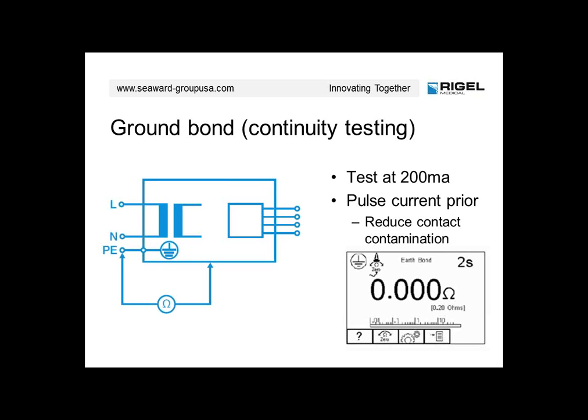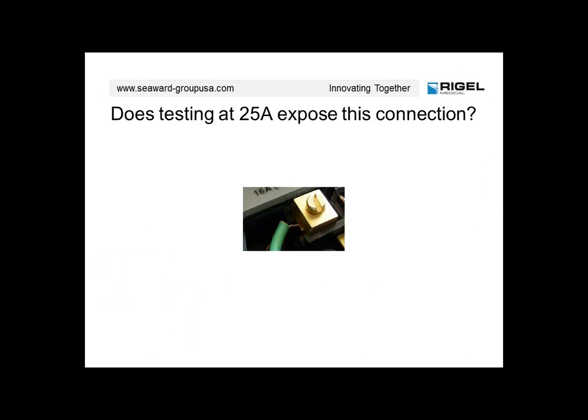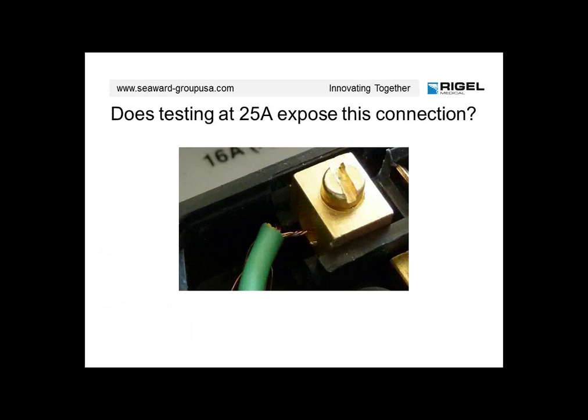However, testing would also show that testing at less than 8 amps will not break down any contamination on the contacts, any film resistance. So what is done here is a small pulse current is set for a small duration, high current, to burn through, if you will, any contamination. And then the actual testing is done at 200 milliamps. Testing that we've done would say that 25 amps may not be the best current to do your testing at.